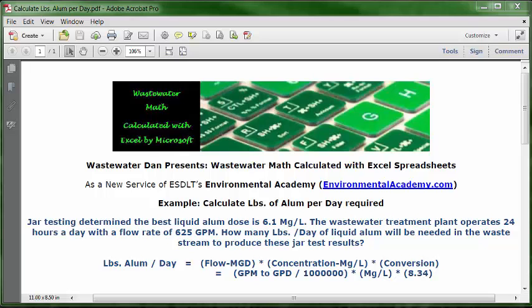Today's problem reads: jar testing determined the best liquid alum dose is 6.1 mg/L. The wastewater treatment plant operates 24 hours a day with a flow rate of 625 GPM. How many pounds per day of liquid alum will be needed in the waste stream to produce these jar test results? This problem uses the standard waste stream version of the pounds per day calculation formula.